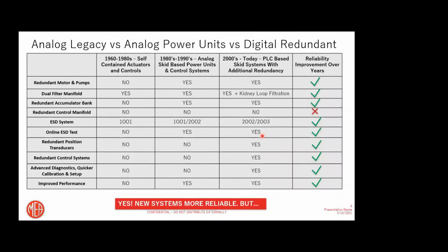So how did we actually try to improve the reliability of these units? Let's look from the beginning, where we had self-contained electrohydraulic actuators, then we went to analog-based power control units, and then PLC-based skids. Let's go one by one and figure out what's been improved and what's not. Redundant motor pump assemblies: yes, it's been improved, because before we didn't have redundancy, now we do.